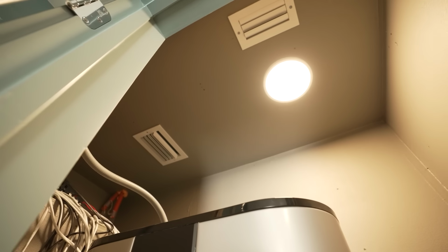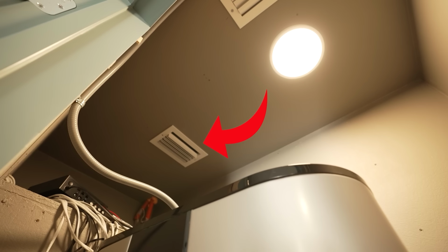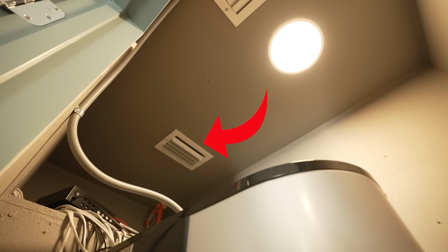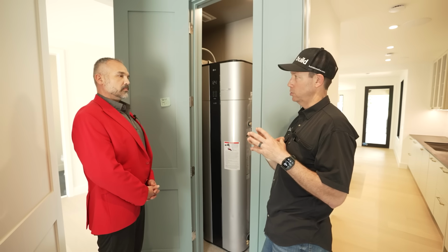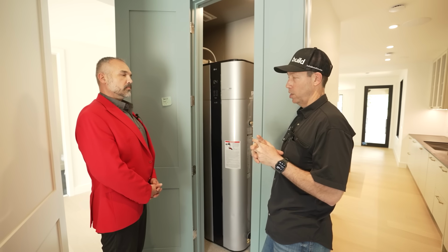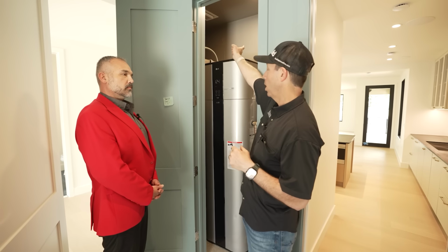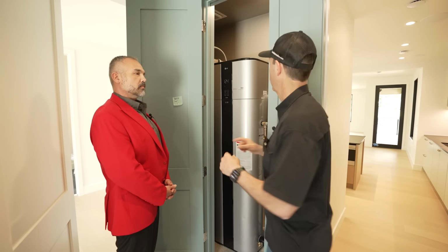Absolutely. So, now you asked about the vents. The vent on the left is my Santa Fe dehumidifier output. Okay. So that's a smallish unit. I think it's an 80 pint unit, probably 100-ish CFM. I'd have to look up the exact spec. So when it's running, it's gonna dump hot dehumidified air in this closet. Again, adding some extra heat to the space.